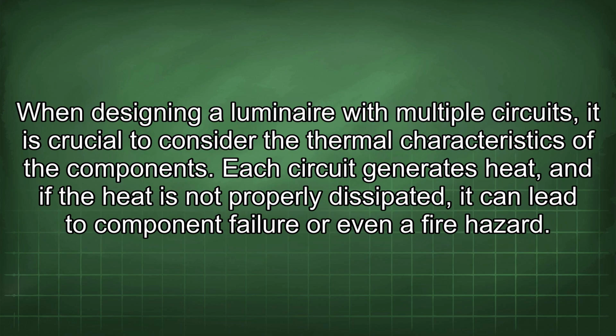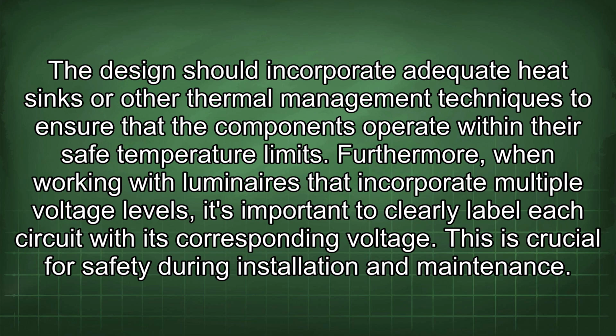When designing a luminaire with multiple circuits, it is crucial to consider the thermal characteristics of the components. Each circuit generates heat, and if the heat is not properly dissipated, it can lead to component failure or even a fire hazard. The design should incorporate adequate heat sinks or other thermal management techniques to ensure that the components operate within their safe temperature limits.